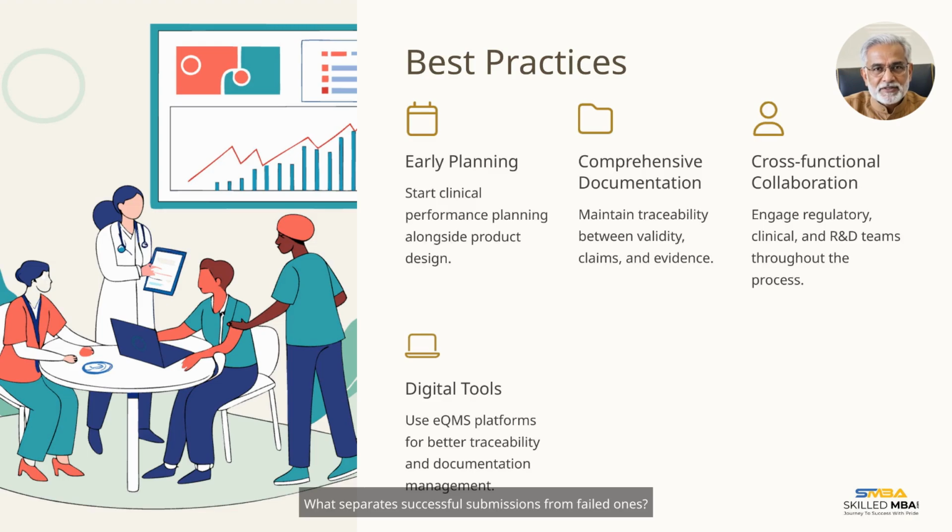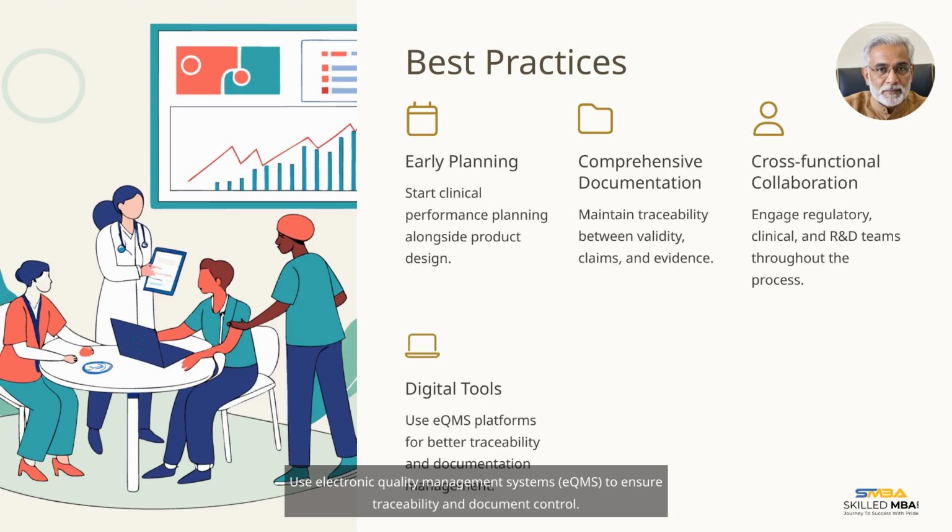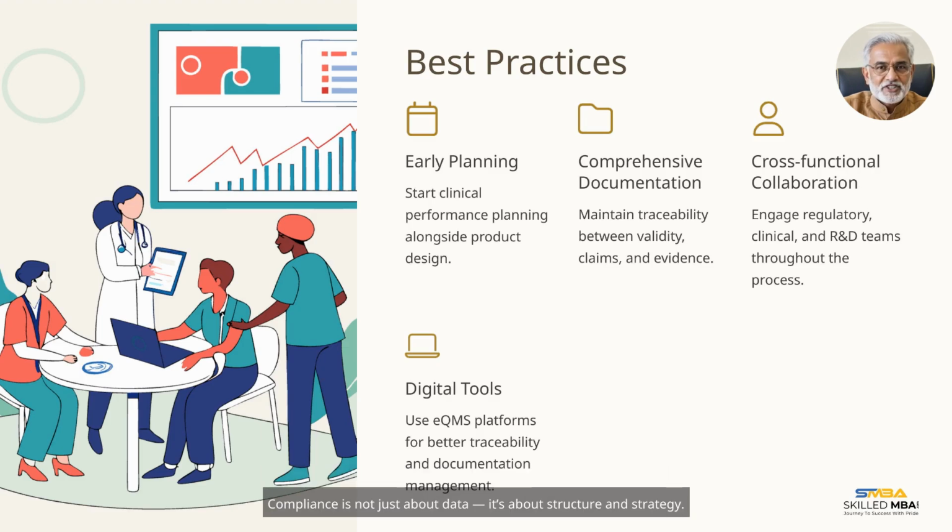What separates successful submissions from failed ones? Early planning. Start building your clinical performance plan alongside product design. Comprehensive documentation. Connect performance claims to evidence and keep the paper trail clear. Cross-functional collaboration. Involve clinical, regulatory, quality, and technical teams from day one. Digital tools. Use electronic quality management systems, EQMS, to ensure traceability and document control. Compliance is not just about data, it's about structure and strategy.